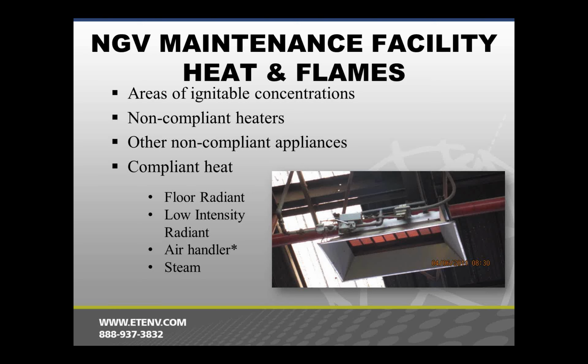What else could be non-compliant that we often run into are used oil burners and pressure washers that would be heated by maybe a natural gas pressure washer. So you have to be careful about those too. And the rules are a little bit tricky in that they say that you can't have these systems any place that there are ignitable concentrations of gas. And it's been sort of industry practice to assume that your entire shop is subject to ignitable concentrations of gas unless you can make a good argument otherwise. And we have made that argument in some cases.